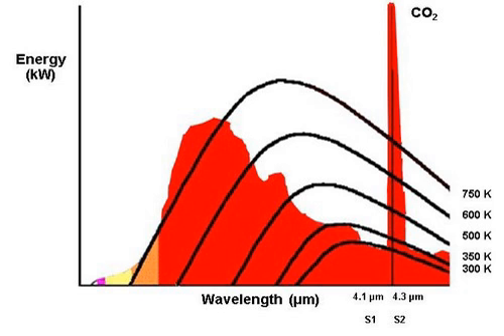Multi-wavelength or multi-spectral detectors such as 3IR plus UV and UVIR are an improvement over their IR-only detector counterparts, which have been known to either false alarm or lose sensitivity and range in the presence of strong background noise such as direct or reflected light sources or even sun exposure. IR detectors have often relied on infrared bulk energy growth as their primary determining factor for fire detection, declaring an alarm when the sensors exceed a given range and ratio. This approach, however, is prone to trigger from non-fire noise, whether from blackbody radiation, high-temperature environments, or simply changes in the ambient lighting.